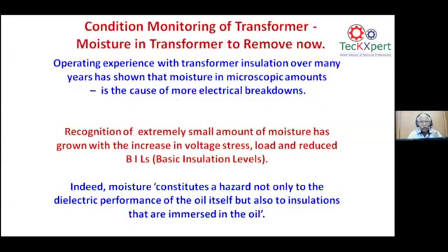So for the given transformer, the condition monitoring of the transformer. All the other parameters we take care of from the maintenance side: on the thermal imaging side, what are the switching, what are the contacts, what is the body of the transformer, what is the PD, the basic insulation levels, everything we are taking over. But the moisture, especially now at the time of the COVID crisis, and even in many of the power and distribution transformers, you find the moisture is increasing in the transformer in microscopic amounts.